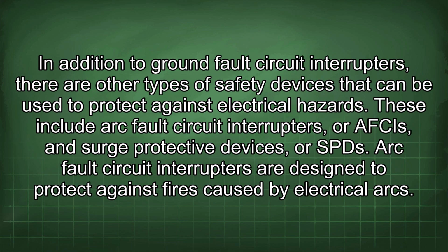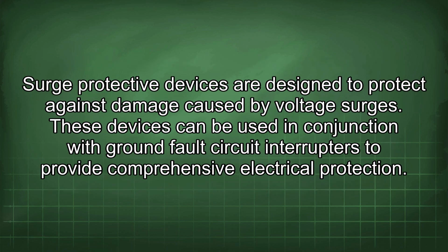In addition to ground fault circuit interrupters, there are other types of safety devices that can be used to protect against electrical hazards. These include arc fault circuit interrupters, or AFCIs, and surge protective devices, or SPDs. Arc fault circuit interrupters are designed to protect against fires caused by electrical arcs. Surge protective devices are designed to protect against damage caused by voltage surges. These devices can be used in conjunction with ground fault circuit interrupters to provide comprehensive electrical protection.